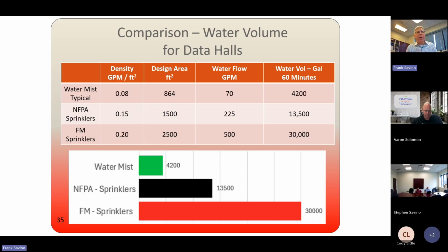Let's compare that to sprinklers. NFPA 13 for a data center: you're looking at a 0.15 density. Your design area is 1,500 square feet.